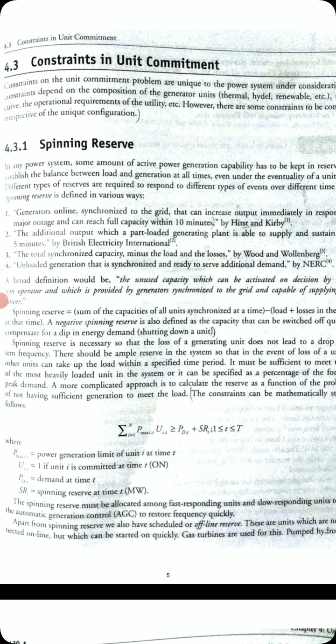So let us see some of the definitions given to the spinning reserve. First one is generators online, synchronized to the grid, that can increase the output immediately in response to a major outage and can reach full capacity within 10 minutes. Another one is the additional output which a part loaded generating plant is able to supply and sustain within 5 minutes. Other one is the total synchronized capacity minus the load and the losses. Very simple definition this is. And another one, the unloaded operation that is synchronized and ready to serve additional demand. So many ways are given for the definition of the spinning reserve.